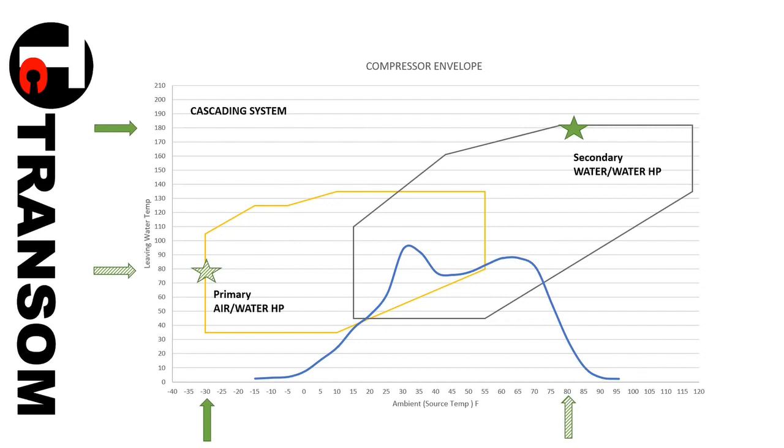But now that you are working for it, you can do 160, and they found that the piping was big enough in the radiators and so on that it basically heated the school. They would get little longer runs and so on out of it, but it would keep up with that. And then the other thing they did with it was the peak load shaving, so that when the electrical power usage from the heat pumps and so on got up too high, they would cut them off.